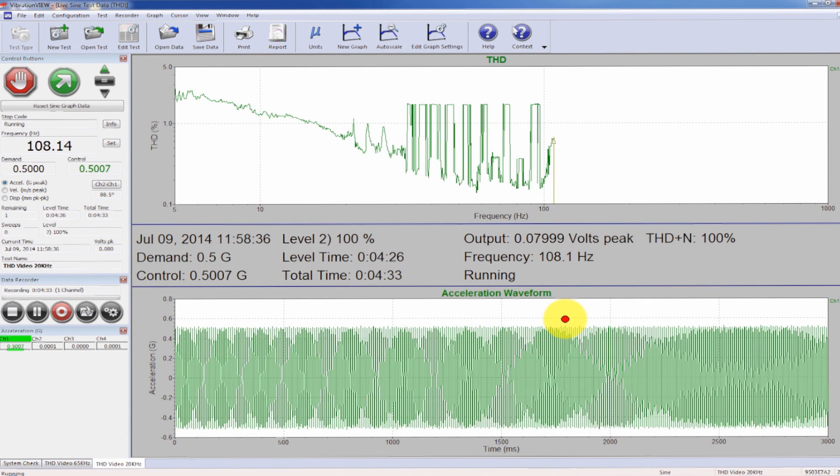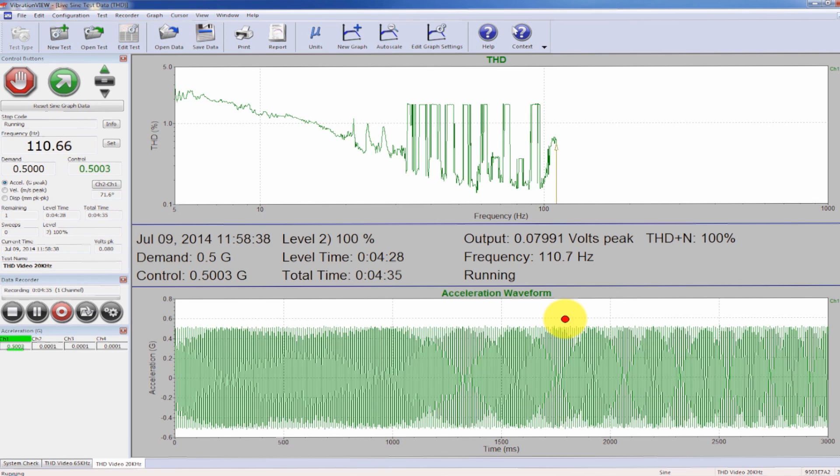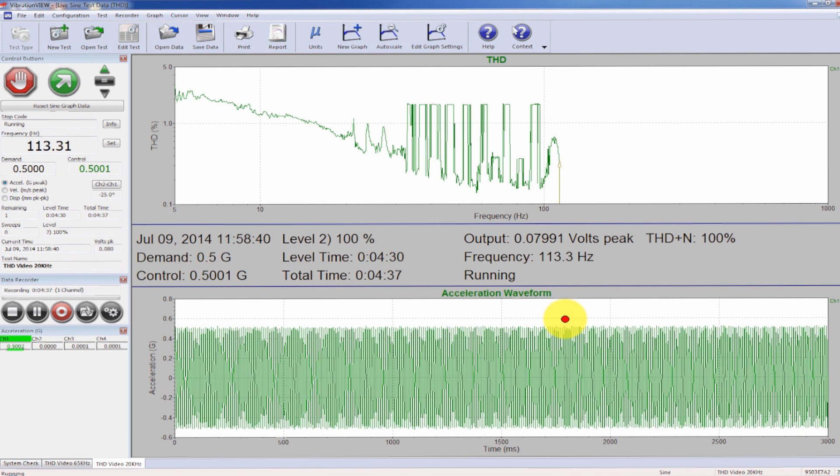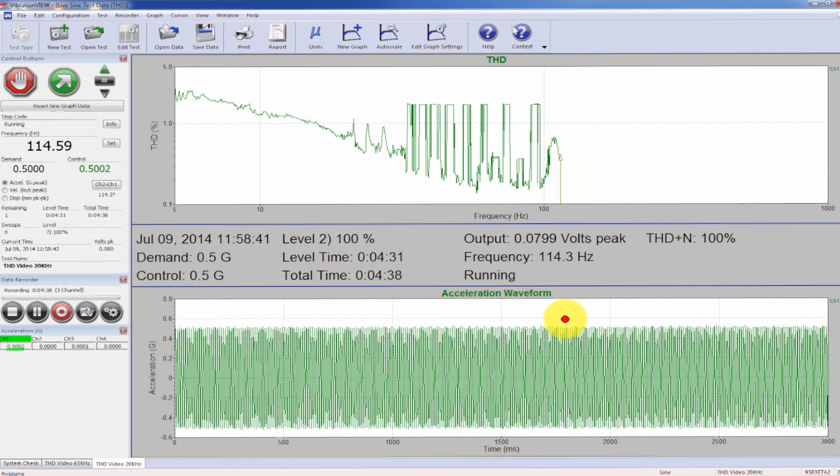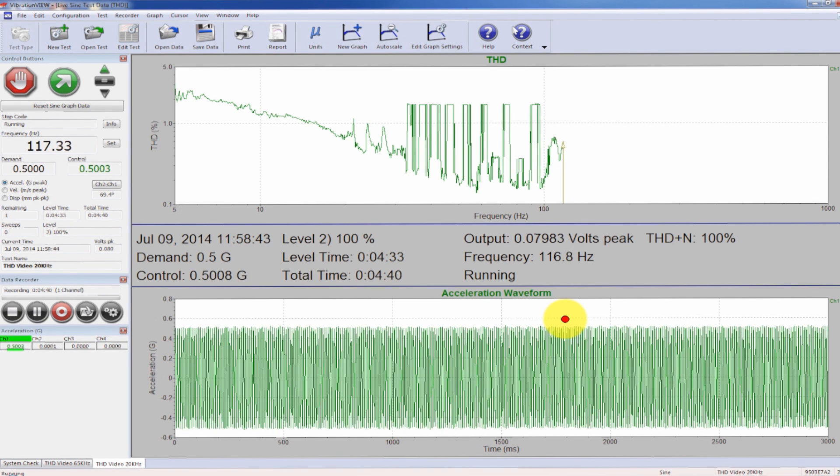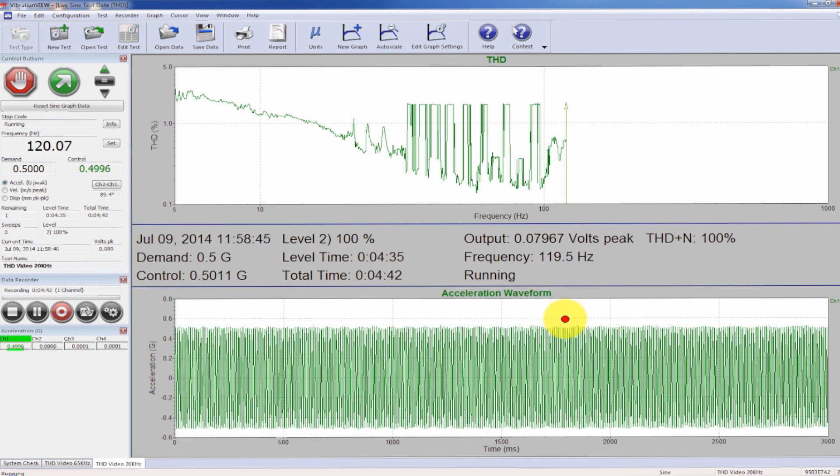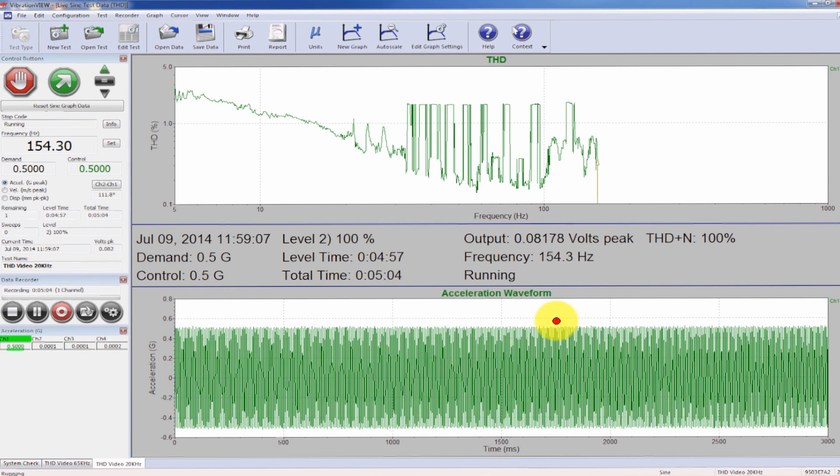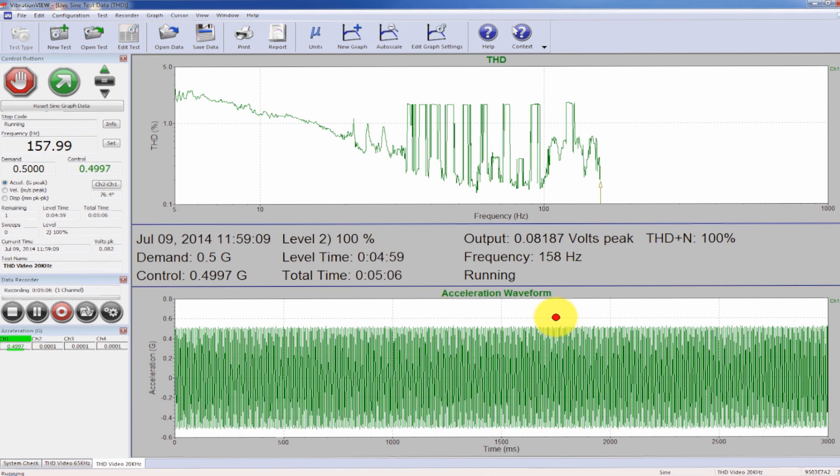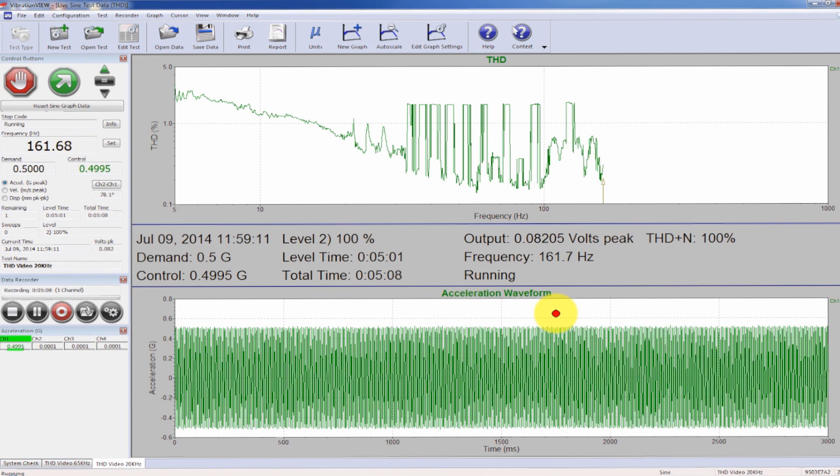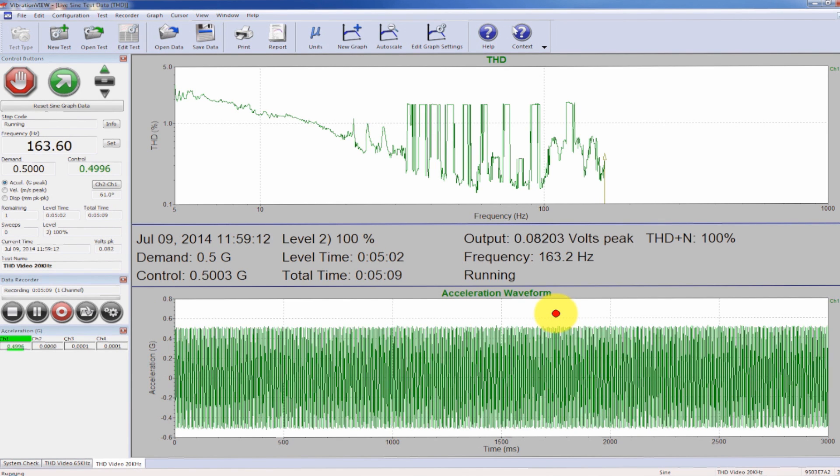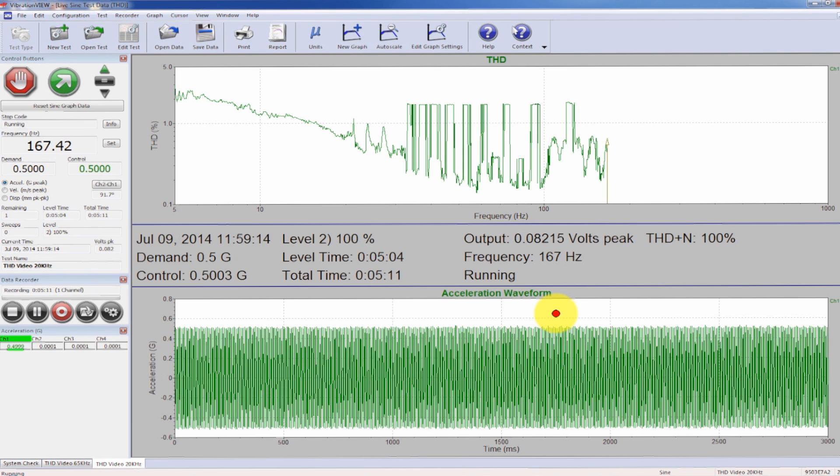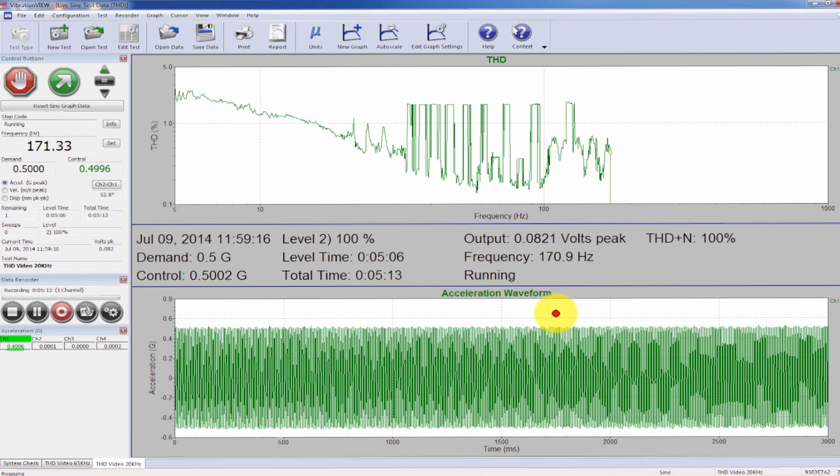We're at a hundred hertz and still operating right at about 1%. Again, very good for this system and certainly acceptable for a shaker system. So anything above 10% may be a fixture issue or the product response is feeding back into that control signal.